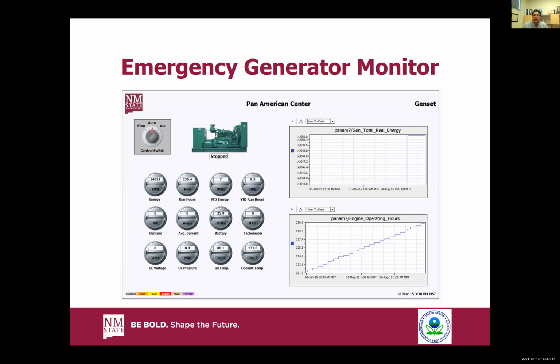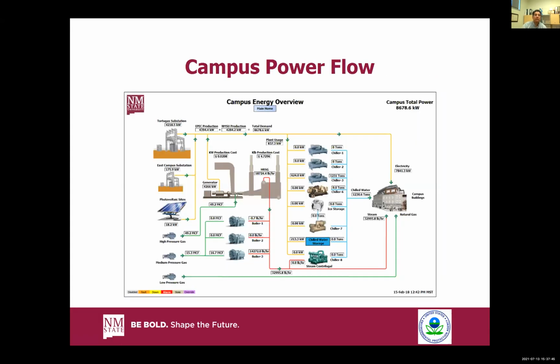More importantly, looking at the dial gauges on the top row, the one on the far right showing year-to-date run hours - we cannot let that get past 500 hours or we're in violation of our EPA air permit, which would be bad. This is how we flag that; we can send alarms via text message or email if numbers start approaching excessive hours. That's our way of being responsible and tying into these types of systems as well.